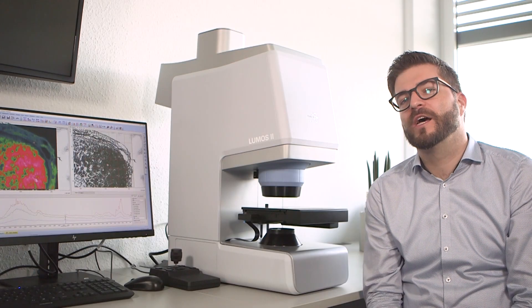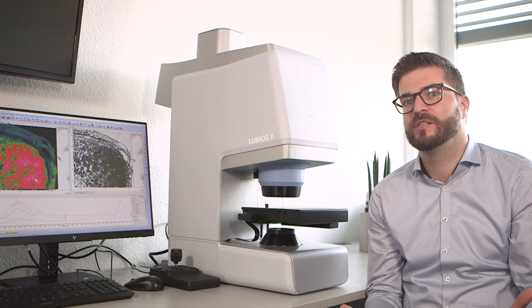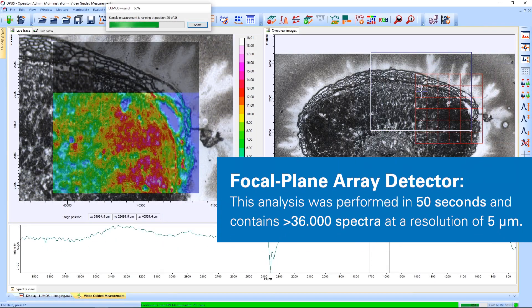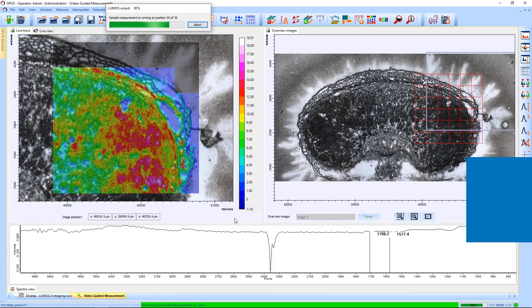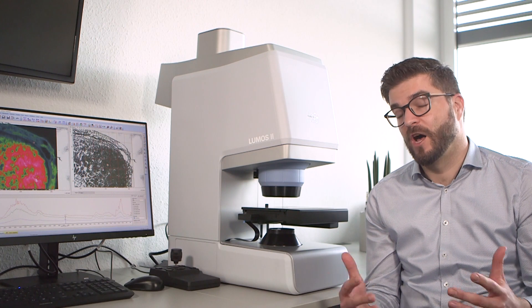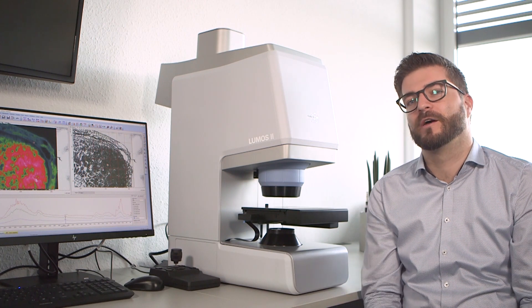Maybe the most exciting feature of the Lumos II is its extremely fast imaging capabilities. Paired with a high-sensitive focal plane-array imaging detector — that's what we call true imaging. A focal plane-array detector can be described as a digital camera in the infrared range. It collects more than 1000 spectra in one single shot, combining high speed and high spatial resolution at the same time.